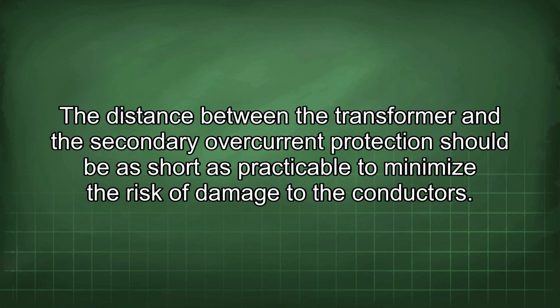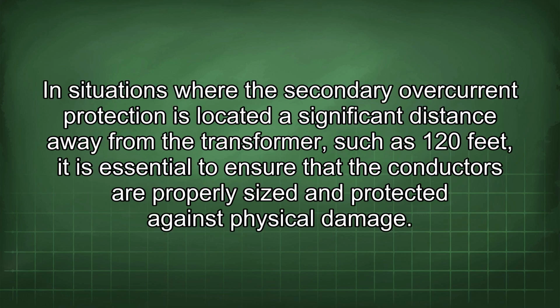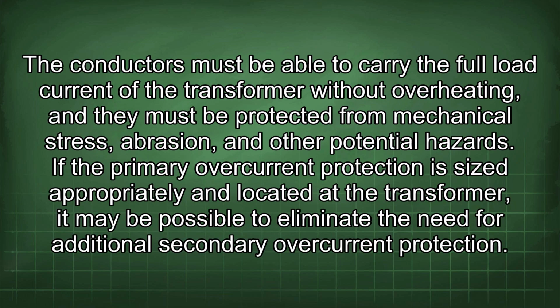The distance between the transformer and the secondary overcurrent protection should be as short as practicable to minimize the risk of damage to the conductors. In situations where the secondary overcurrent protection is located a significant distance away from the transformer, such as 120 feet, it is essential to ensure that the conductors are properly sized and protected against physical damage. The conductors must be able to carry the full load current of the transformer without overheating, and they must be protected from mechanical stress, abrasion, and other potential hazards.